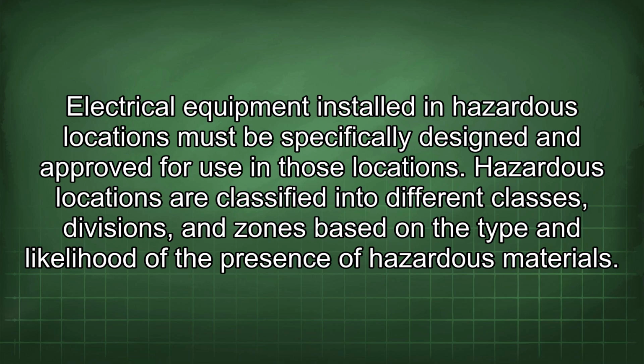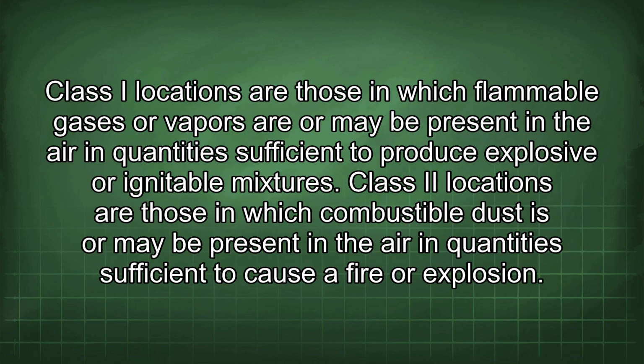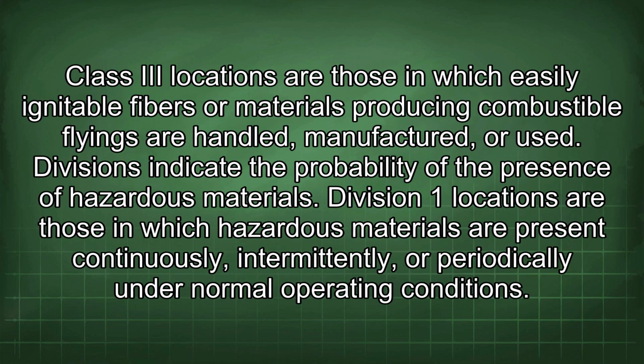Class I locations are those in which flammable gases or vapors may be present in the air in quantities sufficient to produce explosive or ignitable mixtures. Class II locations are those in which combustible dust is or may be present in the air in quantities sufficient to cause a fire or explosion. Class III locations are those in which easily ignitable fibers or materials producing combustible flyings are handled, manufactured, or used.